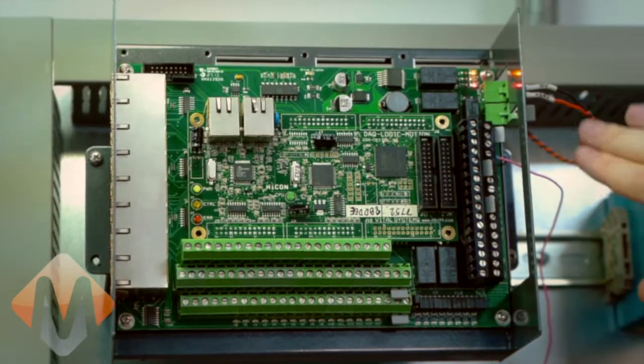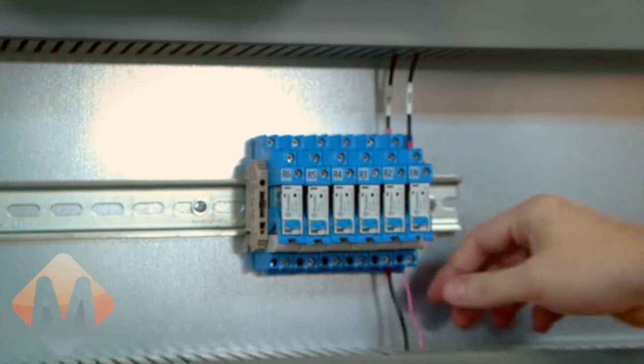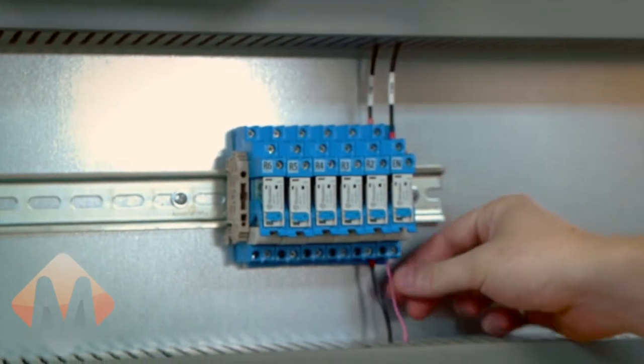From the HiCon, we have the 24 volt enable signal coming here to the enable relay. The enable relay has the 24 volts into one side of the coil, and then your ground here comes up to the ground for the 24 volt power supply.